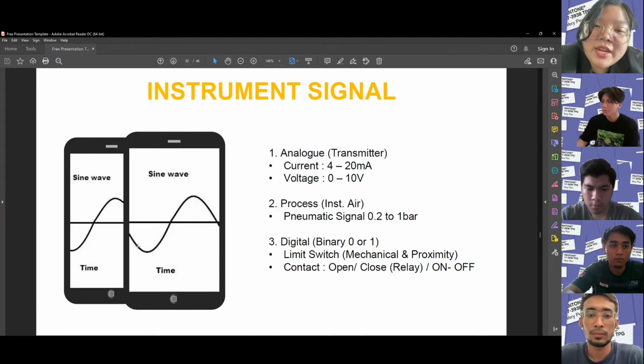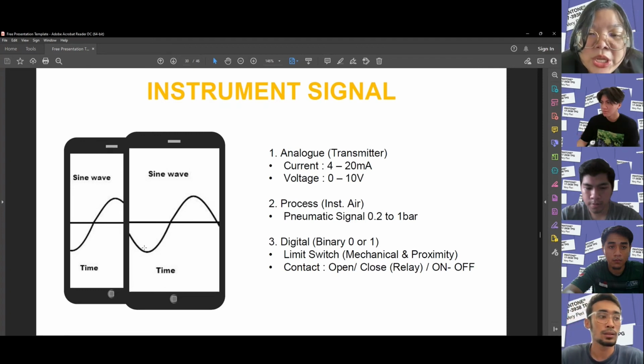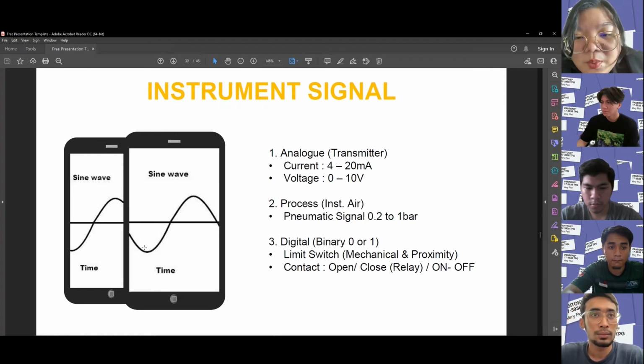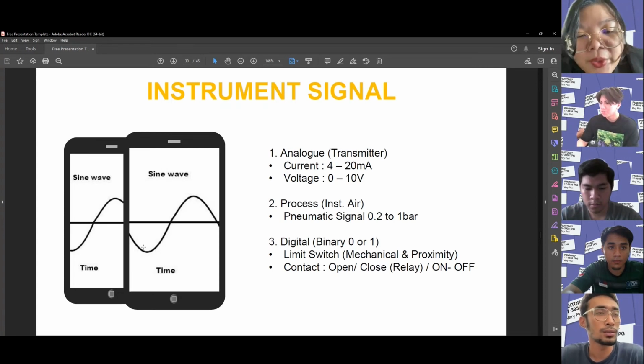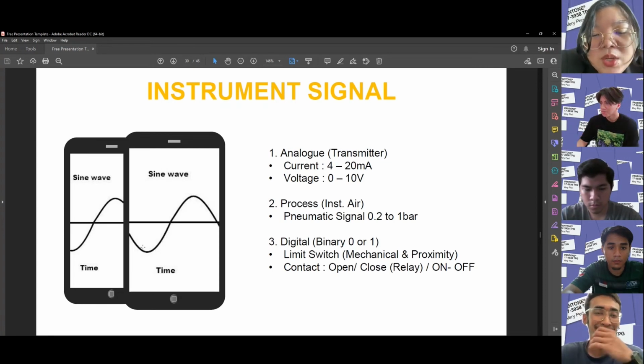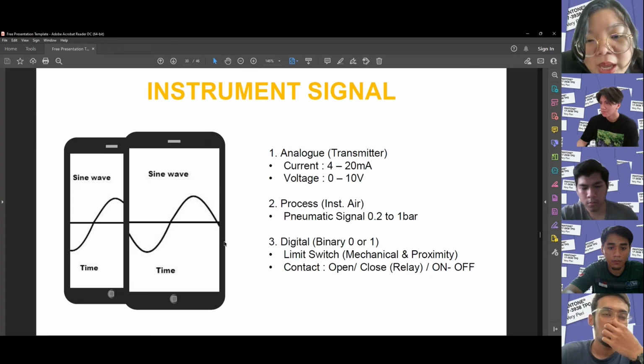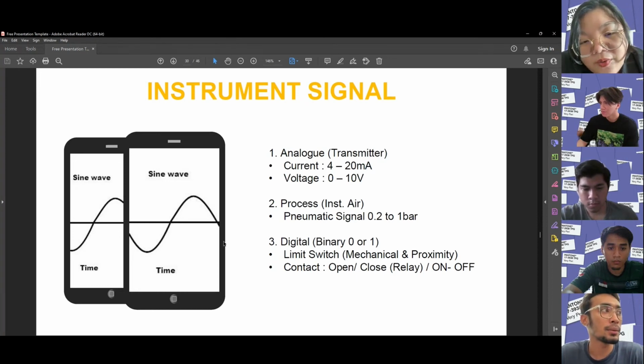So the first one is the analog transmitter. The analog transmitter uses current of about 4 to 20 mA, and the voltage is around 0 to 10 volts. The second one is the process instrument air. They use the pneumatic signal, which is 0.2 to 1 bar. And the third one is the digital binary, 0 or 1. They use the limit switch, which is mechanical or proximity. And the second one is the contact, which is an open or closed relay, on or off.